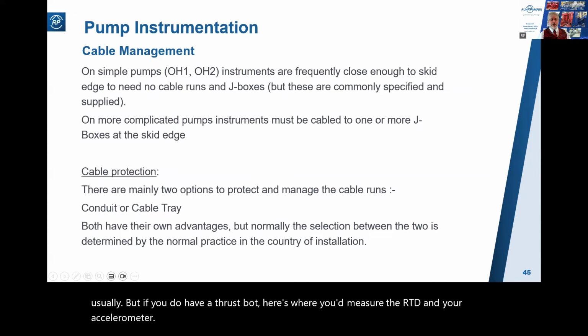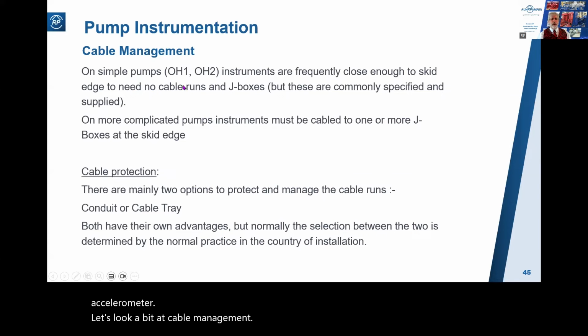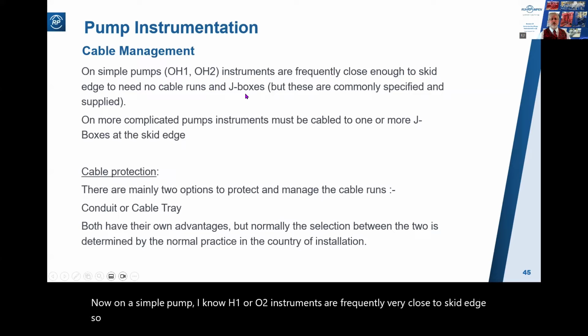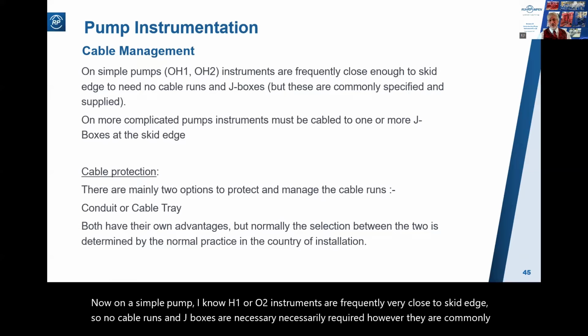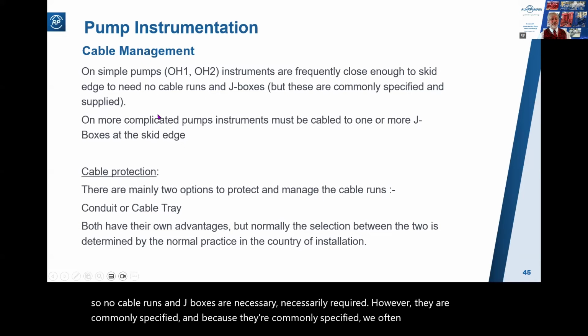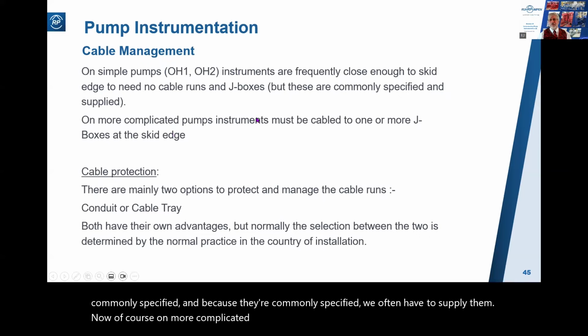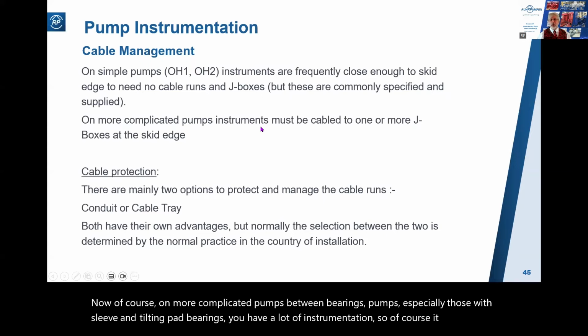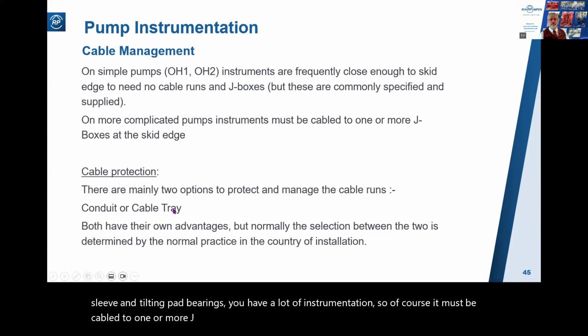Let's look a bit at cable management. Now, on a simple pump, an OH1 or OH2, instruments are frequently very close to skid edge, so no cable runs and J-boxes are necessarily required. However, they are commonly specified, and because they're commonly specified, we often have to supply them. Now, of course, on more complicated pumps, between bearings pumps, especially those with sleeve and tilting pad bearings, you've got a lot of instrumentation, so of course it must be cabled to one or more J-boxes at the skid edge.